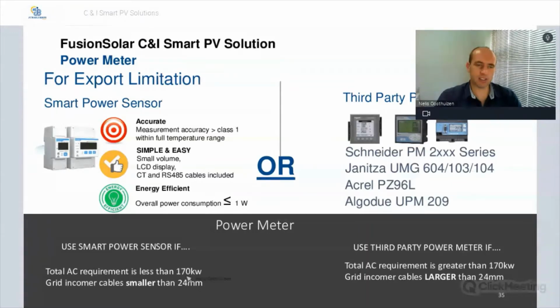A note that I would like to add here is that this AC requirement of less than 170 does not specifically relate only to your PV. So if you only install a 60 kilowatt or 100 kilowatt PV system, but the actual grid requirement of the plant where the system is being installed is more than 200 kilowatt, then this Huawei smart power sensor is not compatible. Then you have to go with a third-party power meter. So when are you going to use a third-party power meter? If your AC requirement is greater than 170 kilowatt, or if your grid incomer cable is larger than 24. I just want to emphasize it again: the 170 kilowatt limit is not the size of the PV system, but the actual AC grid requirement, or the AC size of the actual site that you're installing the system.